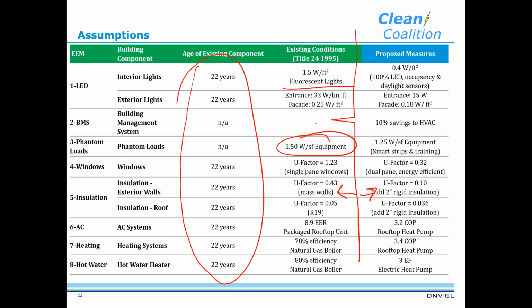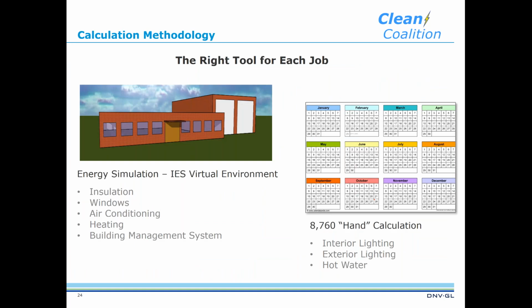Our calculation methodology — this is really important. Energy modeling software is really good at certain things, and for some things it tends to not be the right tool for the job. So we used a variety of 8760 hand calcs — there's 8,760 hours in a year. We used those for interior lighting, exterior lighting, and hot water calculations because it gives you a lot more control, especially on the hot water side. The energy simulation software used in this case was IES's Virtual Environment. It models hot water, but it's a little better to do that outside the software. Energy simulation software is really important for looking at the effectiveness of everything that has to do with weather — that's insulation, windows, air conditioning, heating, and the improved performance when you add a building management system.